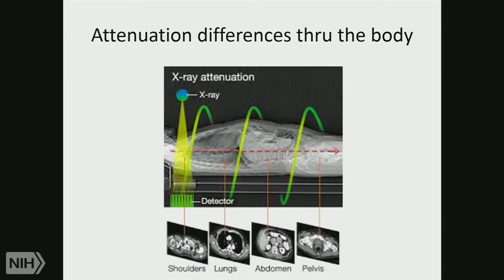And so you can modulate the amount of X-ray for the body part so that the shoulders, where there's lots of bone and soft tissue, might get a relatively high amount of X-ray. The lungs could be dramatically dose reduced. And this can be adjusted to the size of the patient and can be done more or less real time as the patient's on the scanner. So this brings us to the issue of radiation.